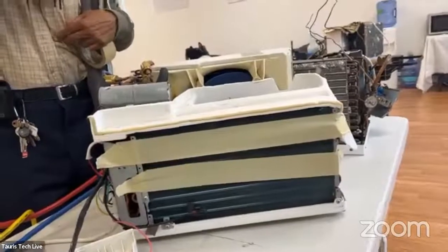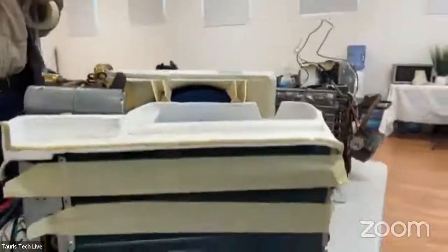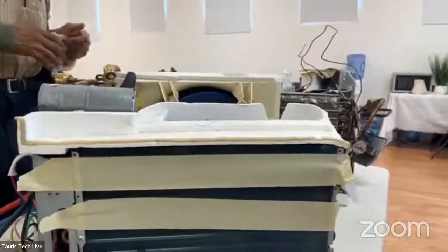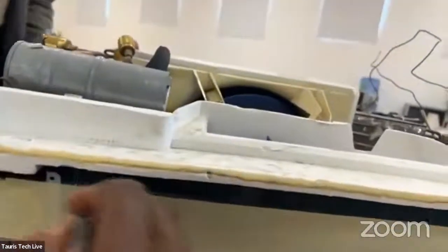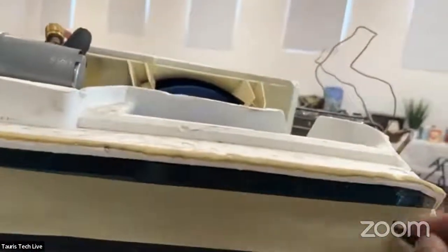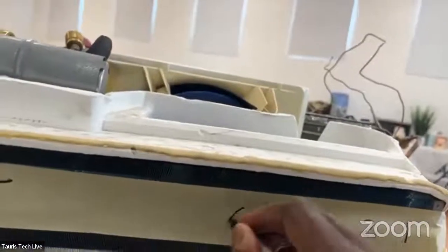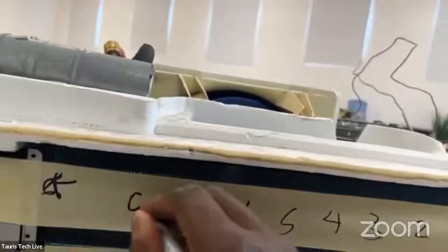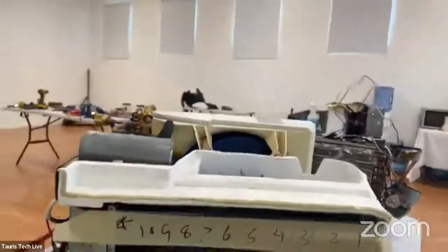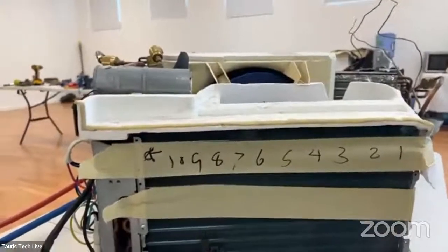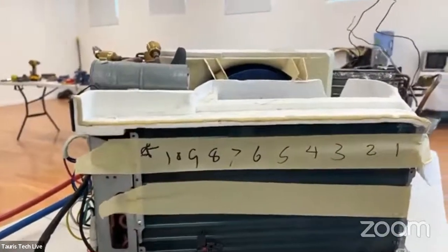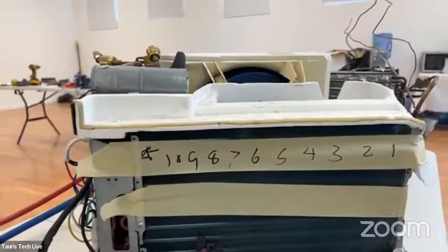This stuff is fundamental to understanding. Okay, so let's say we're just using the last row of the coil for superheat, and the refrigerant is going that way. We start here, 1, 2, 3, 4, 5, 6, 7, 8, 9, 10 degrees of superheat. So as we enter that top portion of the coil, that's where we are absorbing sensible heat, which is superheat because it's above the saturation point, right?